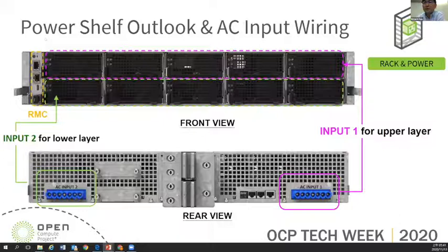And you can see the input of the first layer will connect with AC input 1, and the input of the second layer will connect with AC input 2. And similar to Open Rack V3, we use the 48 volt bus power clip to connect with the bus bar. And we keep some RJ45 here so we can have the CAN bus interface and current sharing signal that can be utilized for multi power shelf parallel operation.